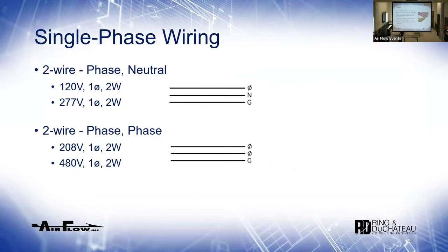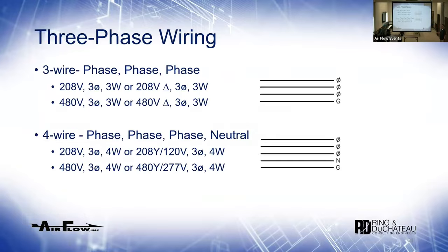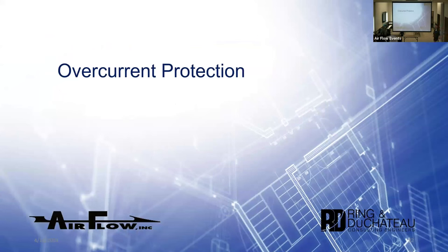The availability of the right voltage in the right place is what we deal with. When getting down into the weeds, HVAC will often ask us, 'What voltage do you want?' — and that's great. But I've had engineers specify 480 and the answer comes back, 'We don't have 480.' Well, you have two options: change the equipment or add a transformer. You're paying the cost one way or another. And 480-volt three-phase is not cheap. So that's sort of the theory section of electricity.